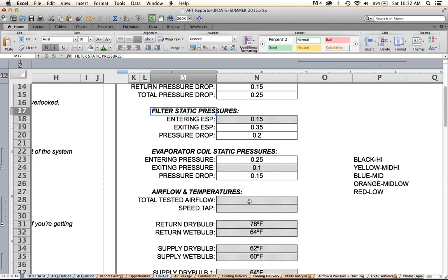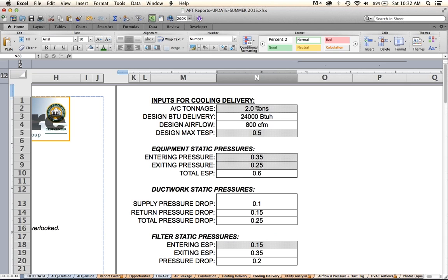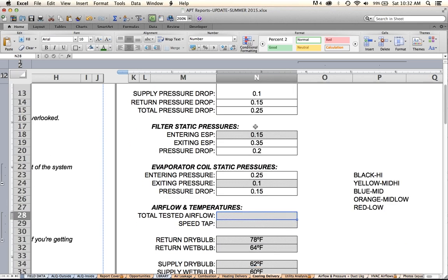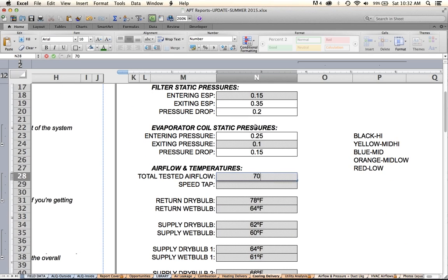It might be a little dirty, might be too small, might be narrow media where I should be using a high, wide media, etc. Total tested airflow. Now, you can see up here I was looking for 800, and it's always important when you're testing to know what number you're looking for before you run the test. That way, if somebody comes in behind you right when you're finishing the test and they say, so what'd you find out? You don't have to say, oh, I need to do some calculations, right? Always try to avoid that. So my total tested airflow, let's say, is 700.